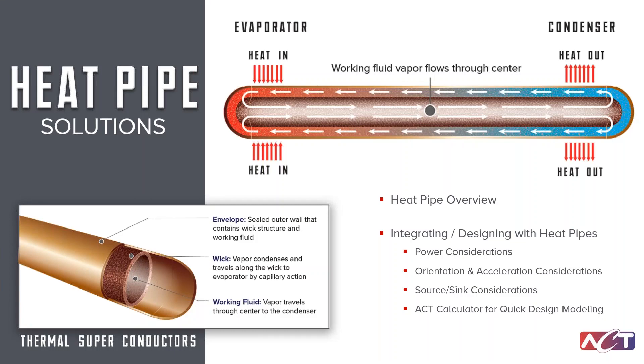So, enter the historic champion of thermal superconductors — the heat pipe. Heat pipes are passively pumped two-phase heat transfer devices that operate in a closed system. The heat pipe is comprised of three components: the envelope, wick, and working fluid. Because a heat pipe is in a vacuum system, the envelope is needed to hermetically seal the heat pipe and also provides some structure. The wick acts as a capillary pump to move liquid to the hot spots, and the working fluid is the two-phase fluid that actually transfers the heat from one end to the other. The heat causes the working fluid to vaporize, then the vapor flows to the cooler end where it condenses, and the condensed liquid returns to the evaporator by gravity or capillary force.